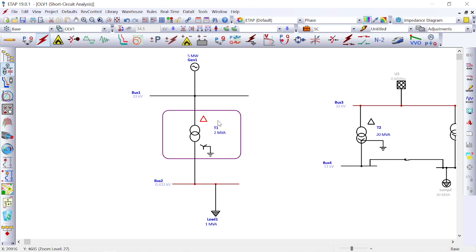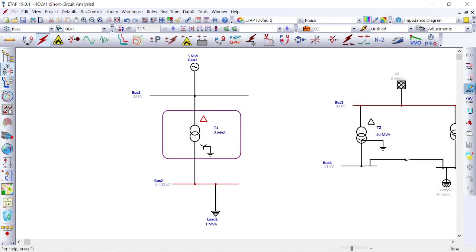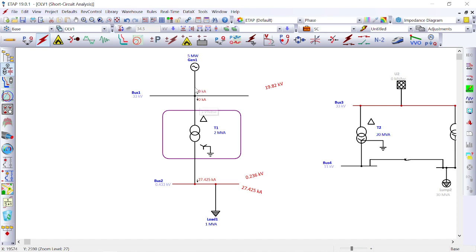Now, changing to delta on the inverter side and star on the load side, then running the line-to-ground fault analysis again for zero sequence current — we can see that initially there was some current, but now there is zero current on the inverter or generator side. The line-to-ground fault current does not flow to the inverter side. So the second reason is that the inverter or generator is protected from zero sequence fault current when delta is selected.